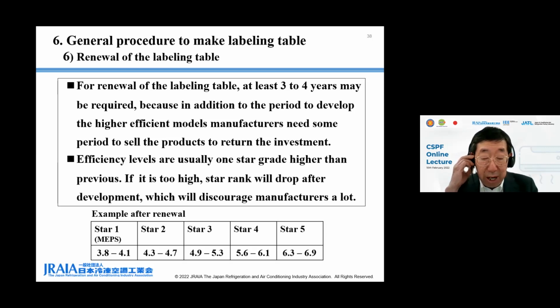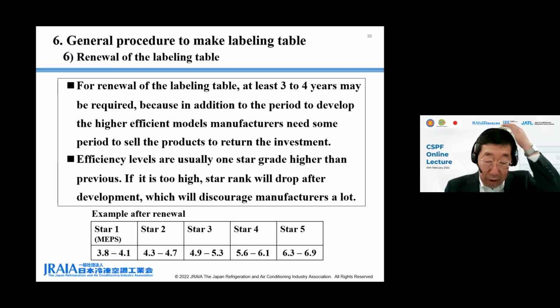If new levels are too high, star rank may drop after development for some manufacturers, which will discourage manufacturers a lot. The table in this page shows an example of new table. New star 1, 2, 3, and 4 levels are same as the old star 2, 3, 4, and 5 levels in the previous page. New star 5 level 6.3 to 6.9 is set to higher level than before, as an example. Of course, CSPF distribution at the time of renewal should be evaluated again before determining new efficiency levels. Next, please.